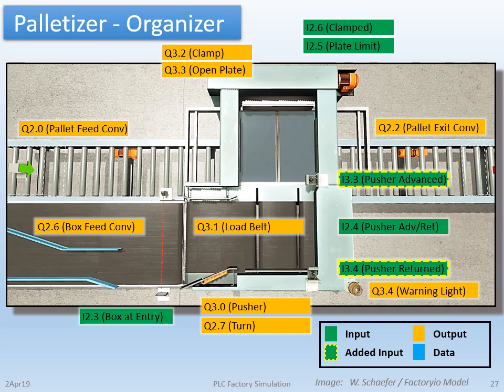If we look at the top view of the elevator, we see that it is essentially the box organizer. Along with the standard supplied inputs, I also added pusher advanced and pusher returned. There is one input for clamped and another for plate at the advanced or returned limit. There's one retroreflective sensor to detect objects just before they enter the elevator pushing area. These are single solenoid type outputs used to advance the clamp and return the plates, advance the turn arm, and to advance the pusher. When they are off, all the cylinders can be considered to be home or in the return position. Outputs also control the pallet feed and exit conveyors, the box feed and load belts. The warning light automatically turns on when the elevator is in motion.